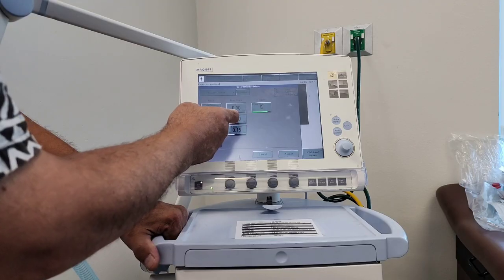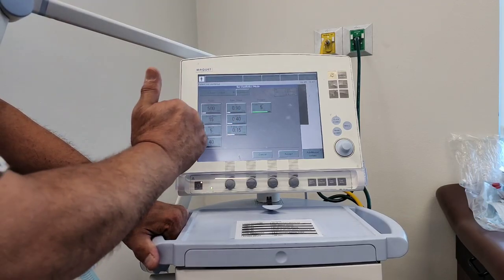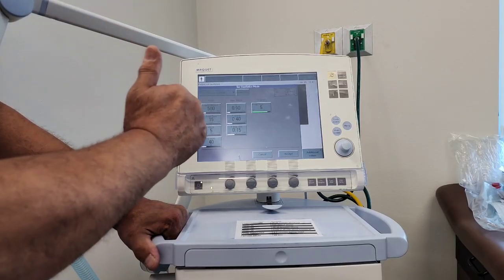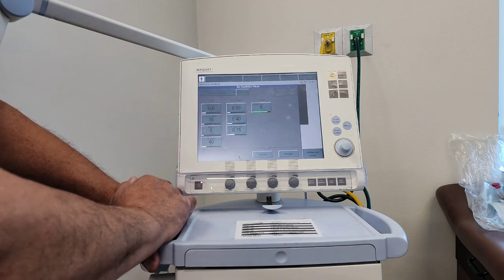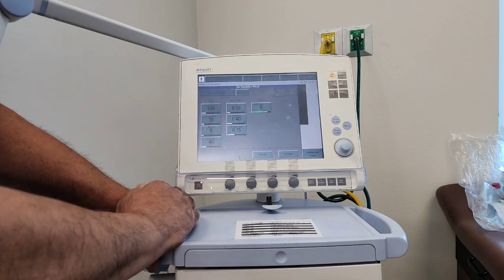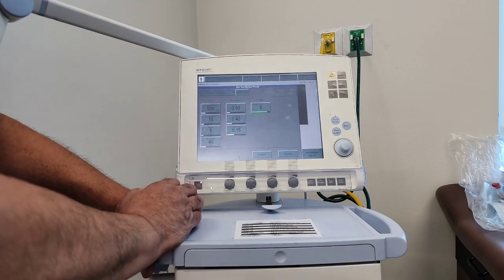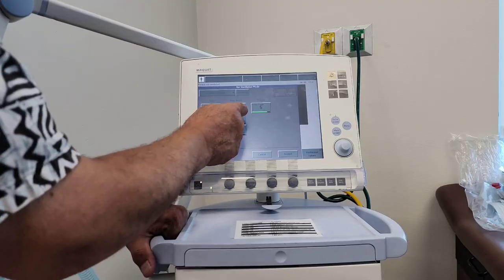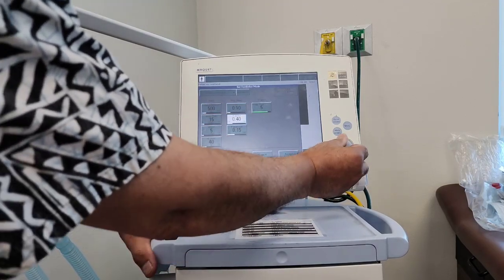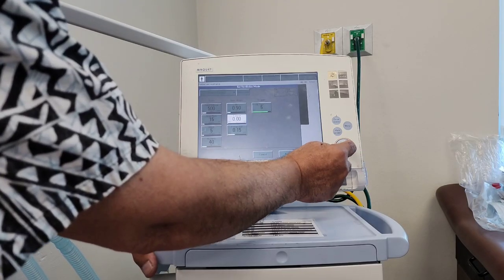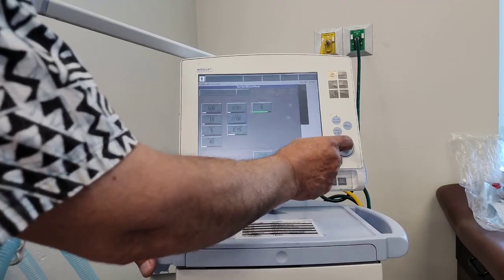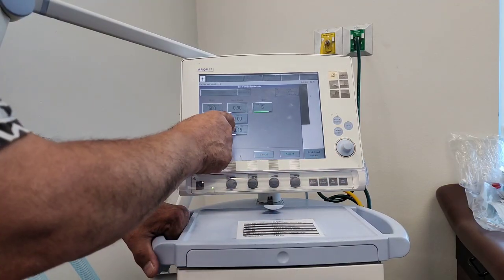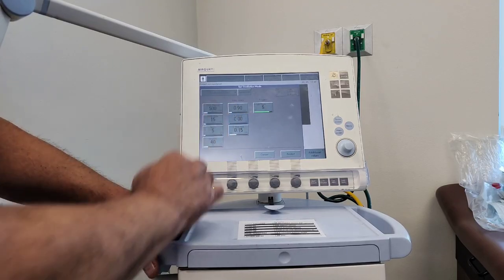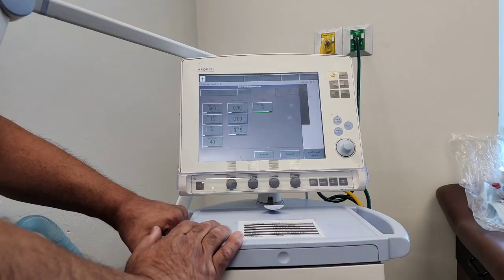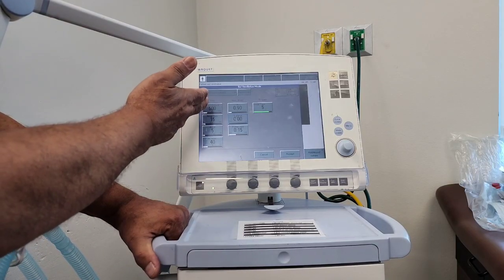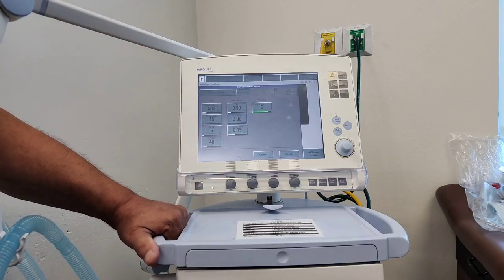There's a T-pause, which we want to always remove. This is a pause at the end of an inspiration. This machine will automatically default to a 0.4 second pause, so it'll hold the breath there for almost half a second. We're going to turn that off. We're going to tap that with this dial over here. We're going to turn it down to 0, and then we can press the button here to accept that value. T, inspiratory rise, that's how quickly we're going to get that tidal volume of 500 into the patient, okay?